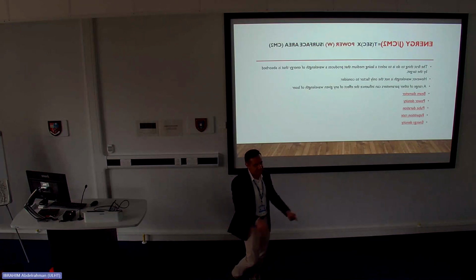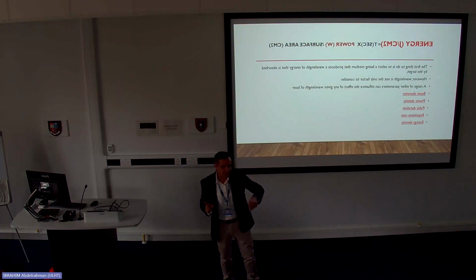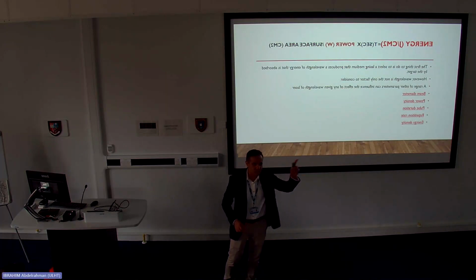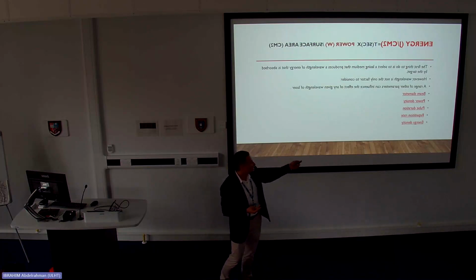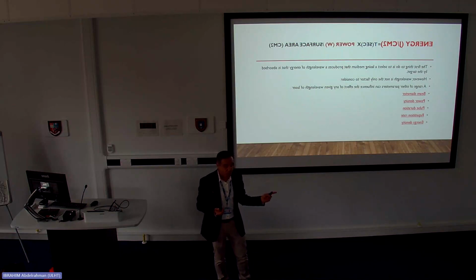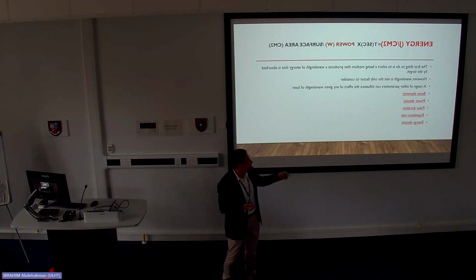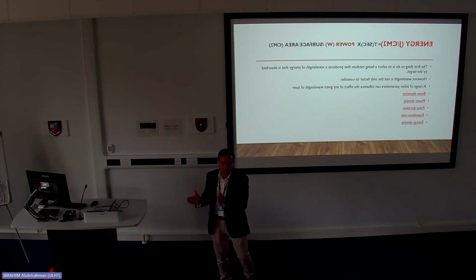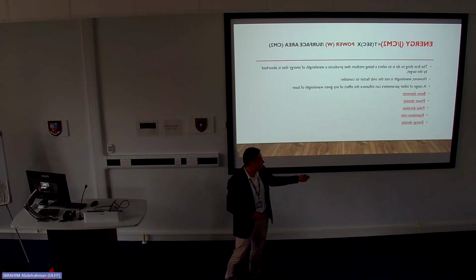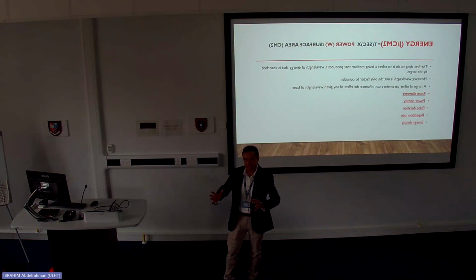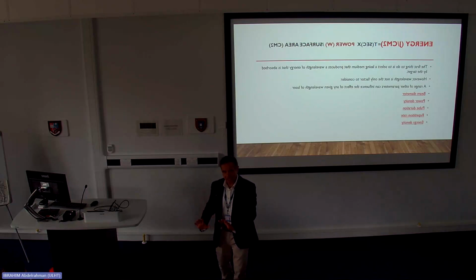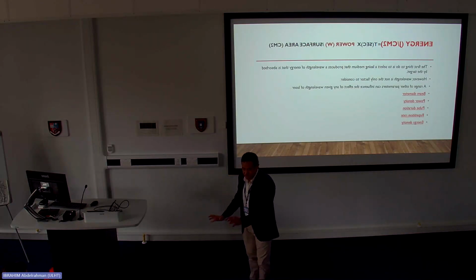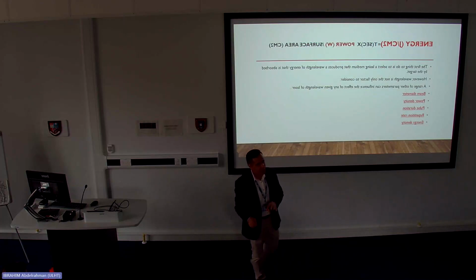So you will find in the board what type of beam you're going to use, which one you're going to pick, the shape of it, and the diameter. It's very important. I'll tell you why, and I'm going to repeat this again. The second thing is the power, and how much you're going to set it to. Then the pulse duration, and the repetition of the pulse as well, so how much rest there will be between each pulse. And then the energy density, which is how much energy you're going to deliver, and depending on this, if it's a low energy, the result will be very different from the high energy.